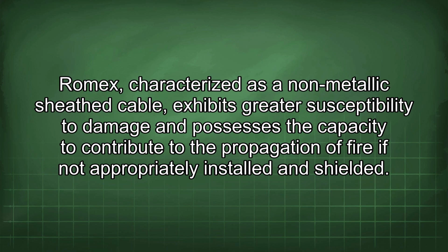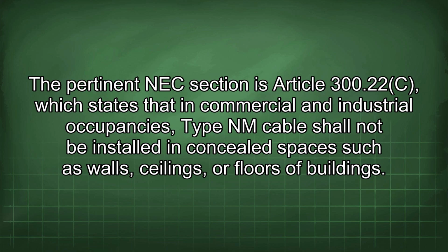Romex, a non-metallic sheathed cable, is more susceptible to damage and can contribute to the spread of fire if not properly installed and protected. The pertinent NEC section is Article 300.22(C), which states that in commercial and industrial occupancies, Type NM cable shall not be installed in concealed spaces such as walls, ceilings, or floors of buildings.